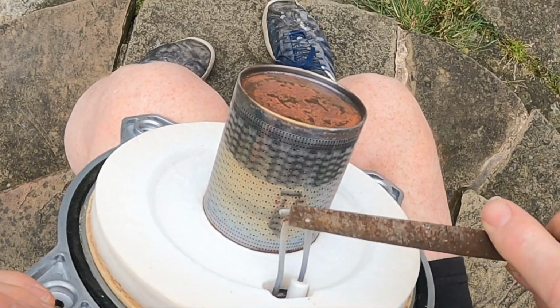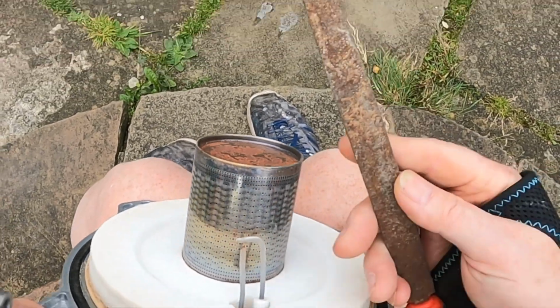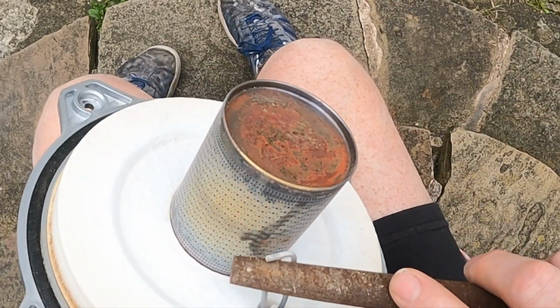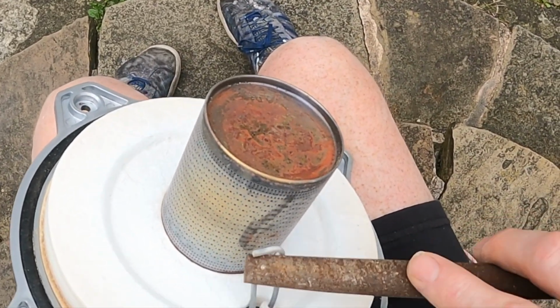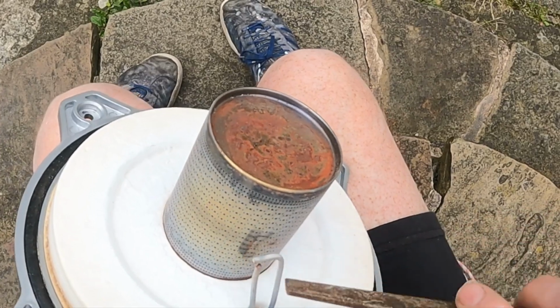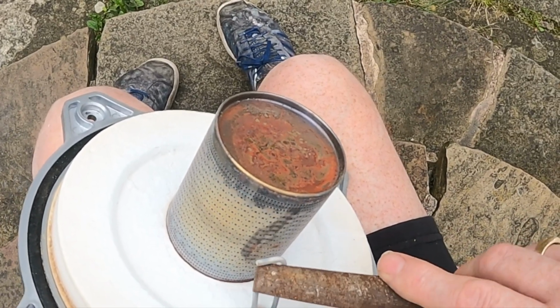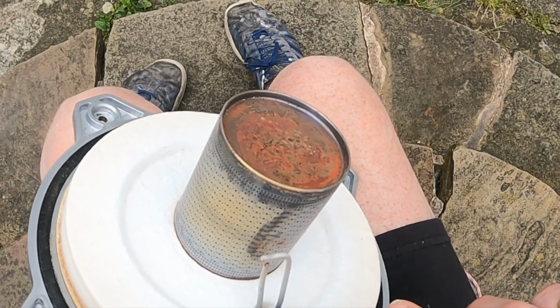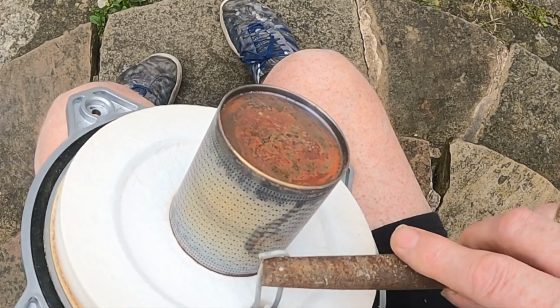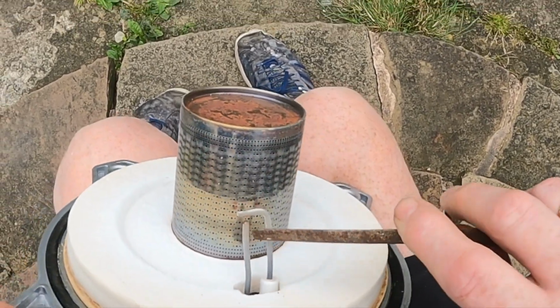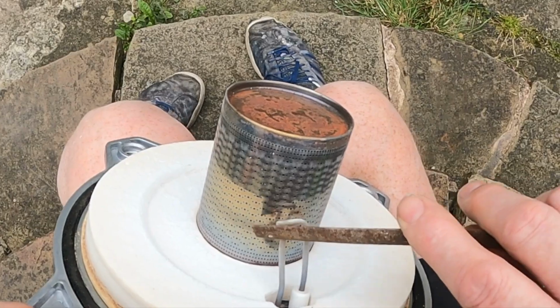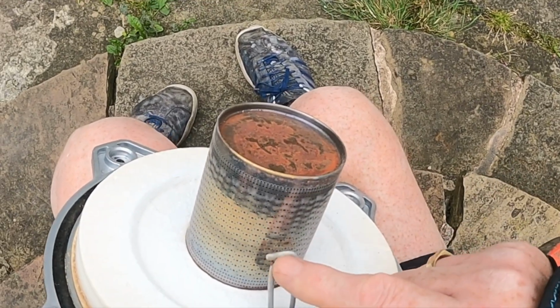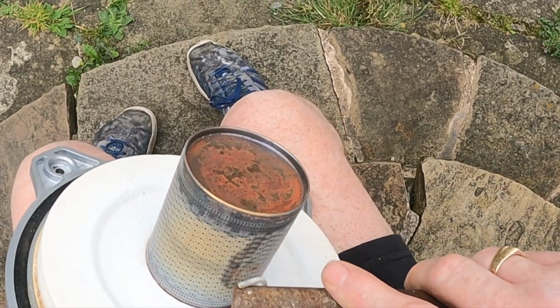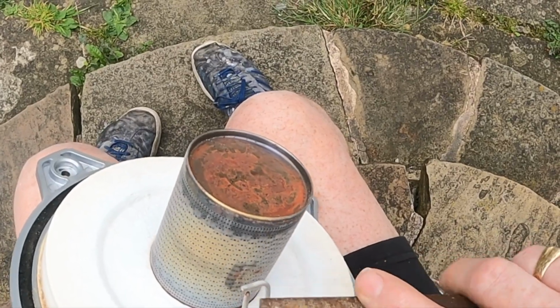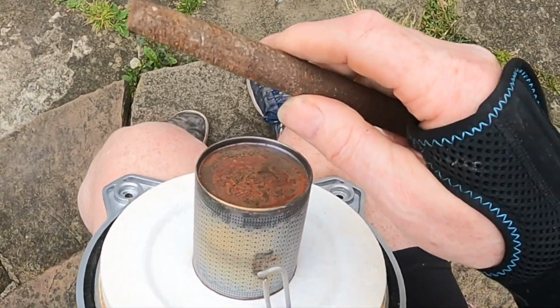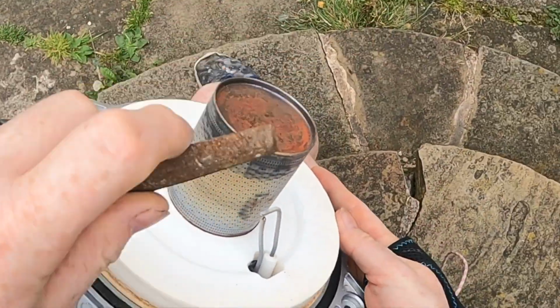Now, the only way you're ever going to clean one of these up is by using a file. You're not going to get it by using wire wool. And obviously you need it to spark on the end, not down here and across here. So always make sure you clean the electrode up. And this gap here should be about 4mm for this boiler. It is slightly different for others, but normally it's about the width of a pound coin.